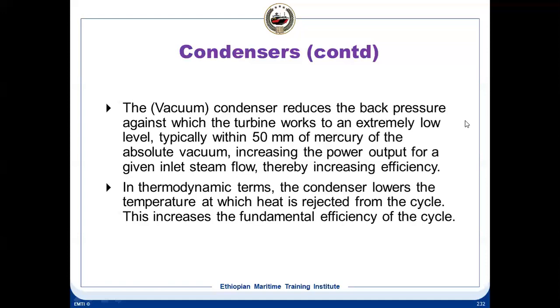That means the condenser is actually working at vacuum. In case the condenser is working at vacuum, even if the inlet steam pressure was at atmospheric, the turbine will work to a certain extent. Why? Because you still have some pressure drop across the turbine due to the vacuum in the condenser. On the inlet side, you increase the energy derived from the steam due to this pressure drop, and your turbine will start spinning that much faster.